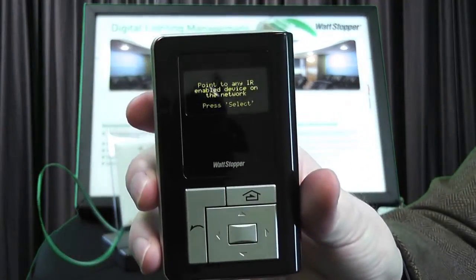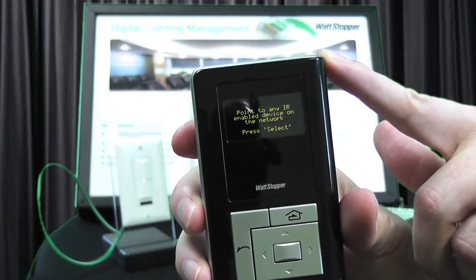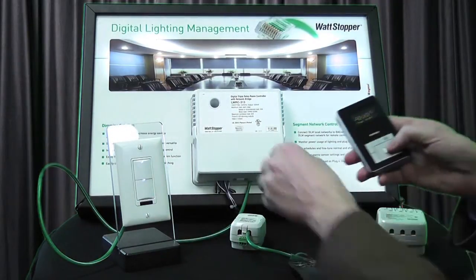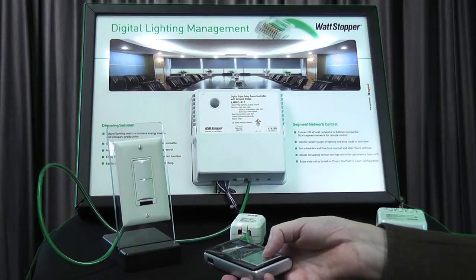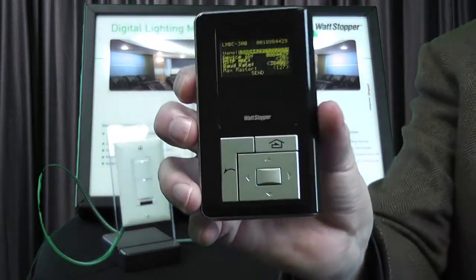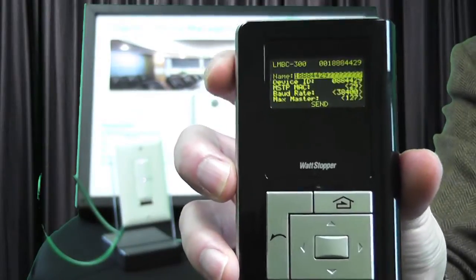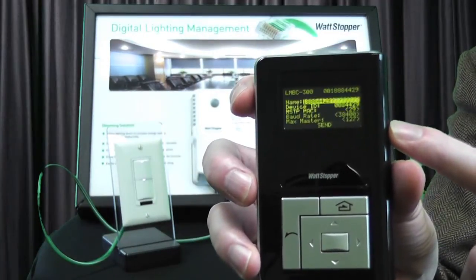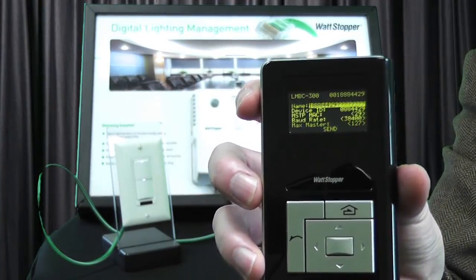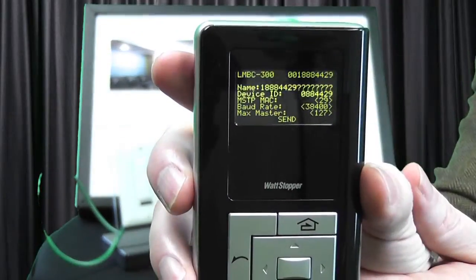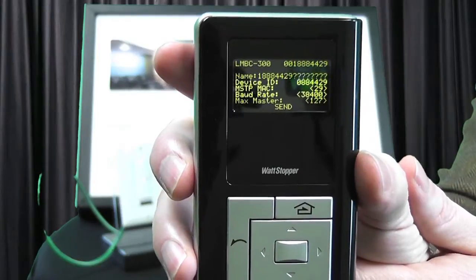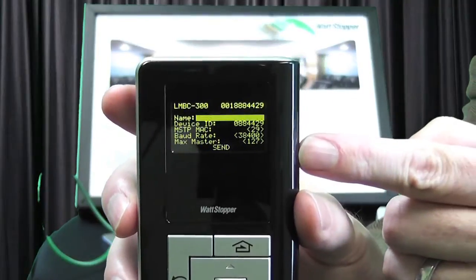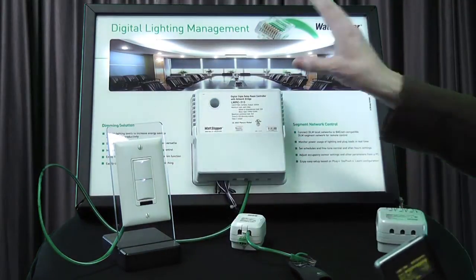I'm just going to choose that, and what it says is: please point this toward any IR device inside the room, and then press select. I've got a switch that's connected to this room controller, this room controller's got a network bridge — I'm just going to press this, and there we go. Now we've actually been able to go in and get a clear identification of what the device ID is, plus what the settings are for how it's supposed to communicate, what speed it's supposed to use, and even an additional address called the MSTP MAC address. Anything I want to change — you see in the little tiny brackets — every one of those is adjustable, and all I'd have to do is make the adjustment on the handheld, hit send, and send that back into the device to make those changes.